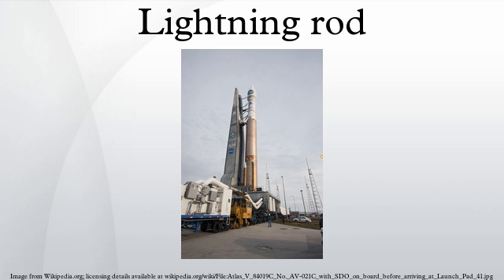Lightning protection of mast radiators. Radio mast radiators may be insulated from the ground by a gap at the base. When lightning hits the mast, it jumps this gap. A small inductivity in the feed line between the mast and the tuning unit limits the voltage increase, protecting the transmitter from dangerously high voltages. The transmitter must be equipped with a device to monitor the antenna's electrical properties. This is very important, as a charge could remain after a lightning strike, damaging the gap or the insulators.